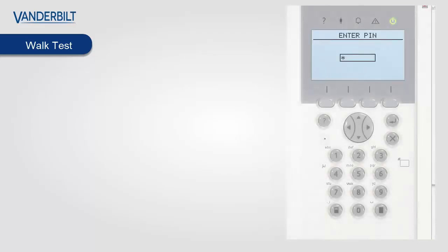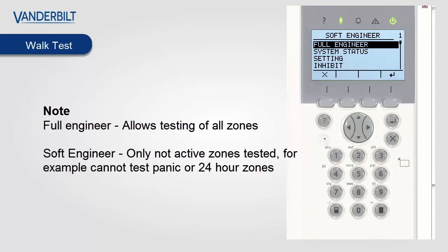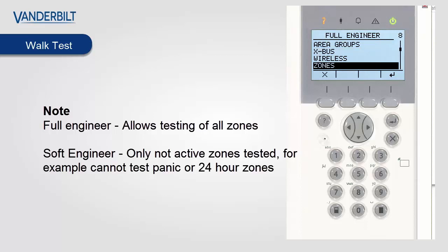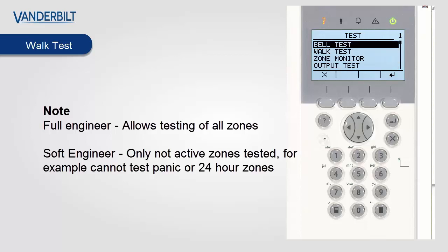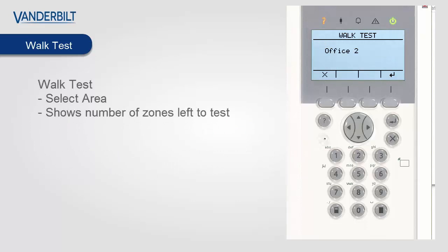You may observe that the number of zones available to test may vary by these menus. This is because alarm zones will not be tested when they are meant to trigger an alarm, so 24-hour alarm zones will not activate in walk test mode. To access this we enter full engineer mode, scroll down to the menu test, select the menu and select walk test. On multi-area systems you must now select the area you wish to test. We select area one where we have two zones to test.